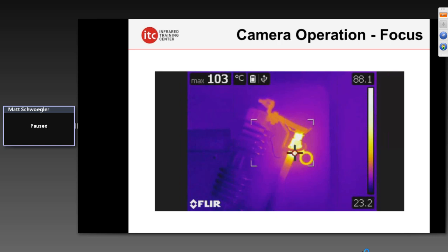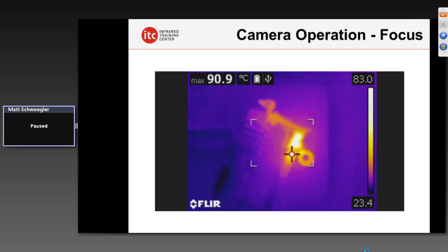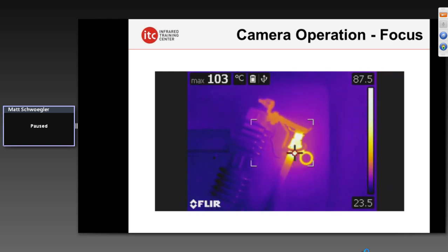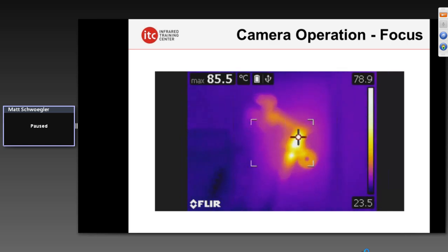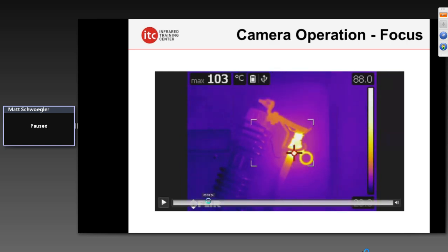But I want to show you how critical having that focus is. If you pull this out of focus ever so slightly, notice how it gets soft — that temperature drops about 12 or 13 degrees Celsius. Multiply that by about two and that's your degree Fahrenheit drop. That is not an insignificant amount. It's amazing just what not having perfect focus will do to the quality of your image. In our training classes, we emphasize the importance of focus — getting great focus to get the best possible data. If it's out of focus, you're not going to be getting an accurate reading.